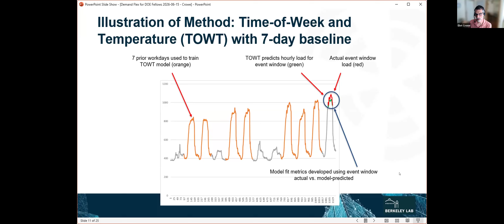Just to be clear, we're checking the baseline model accuracy—no demand response event happened. We're just saying, if we have a building where nothing happened, we use this method to develop a baseline and then predict that 12 to 6 p.m. window on the following day, to see if it was close to the mark. We used that same method for all of the modeling approaches, and that's how we developed the model fit metrics—how close were we?